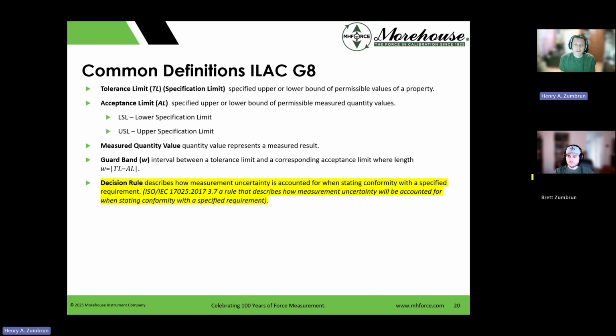Well, that's the tolerance. The acceptance limit is the specified upper and lower bound of permissible measured quantities: lower specification limit and upper specification limit. Measured quantity value is what I actually measured. The guard band is the interval between the tolerance and the corresponding acceptance limit. So the decision rule is how the measurement uncertainty is going to be accounted for.